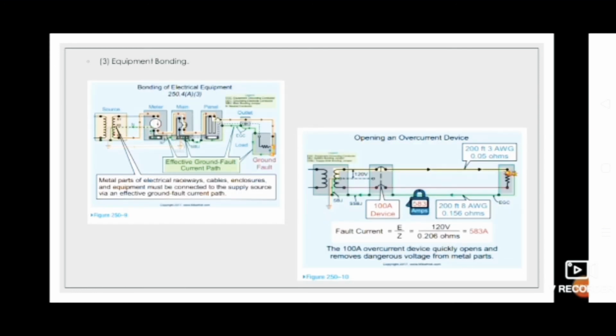Third is equipment bonding. Metal parts of electrical raceways, cables, enclosures, and equipment must be connected to the supply source via the effective ground fault current path. To quickly remove dangerous voltage on the metal parts from a ground fault, the effective ground fault current path must be of substantially low impedance to the source, so fault current will quickly rise to a level that will open the branch circuit overcurrent protection device. And this is a fault current calculation. We can see from the picture it has 583 amperes. The 100 ampere overcurrent device quickly opens and removes dangerous voltage from the metal parts.